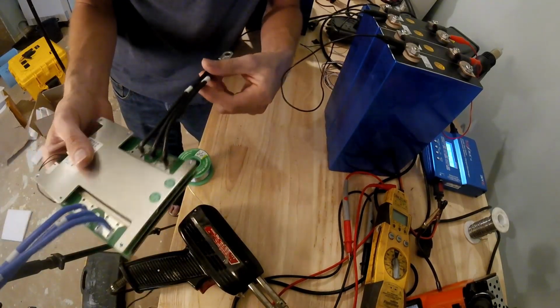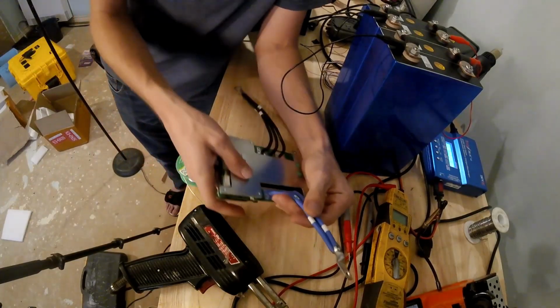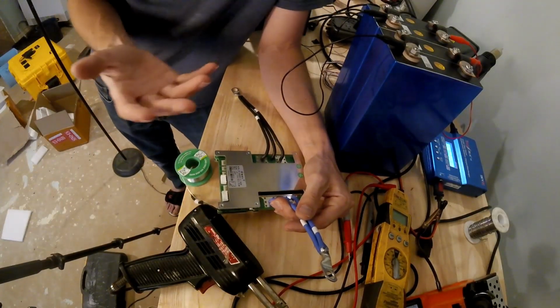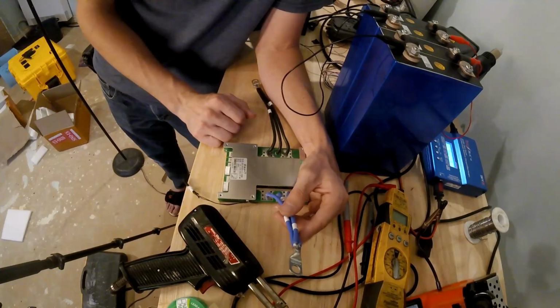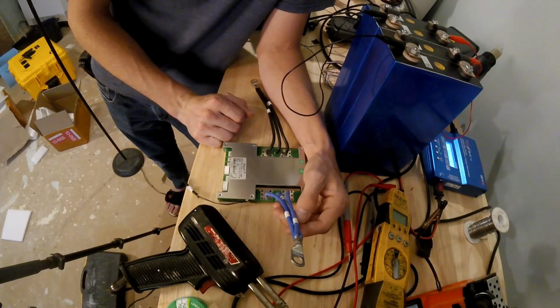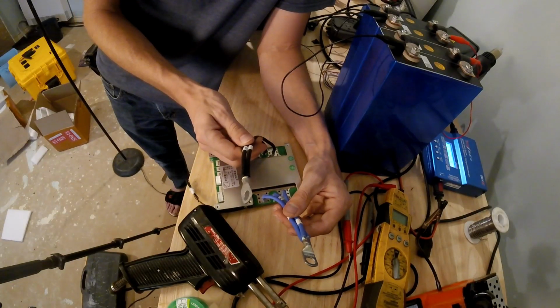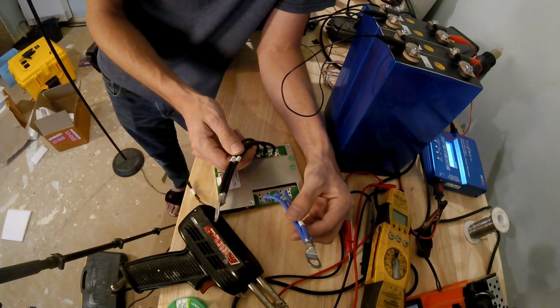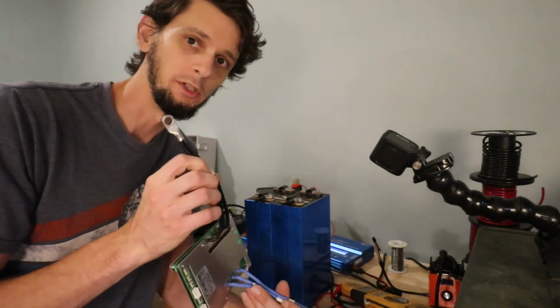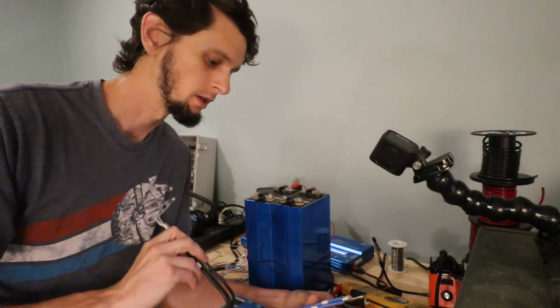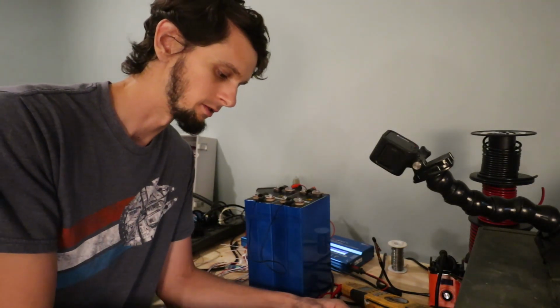When I'm done building this, I'll pull a good 60, 80, 100 amp load on it and get an infrared camera out to make sure I don't have any hot spots, which would indicate I didn't get one of the wires connected, or maybe one wire showing colder than the others, indicating it's not making as good of a connection.